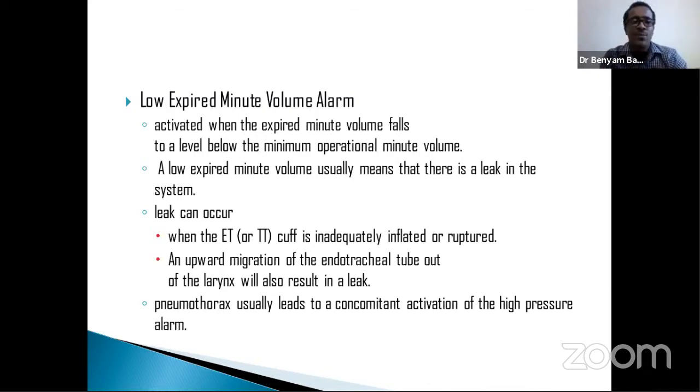Whenever we have a low expired minute volume alarm, usually this alarm goes off when the expired volume falls below a certain level. Technically it means you're losing air somewhere. The air is going into the lungs, but not coming out to be detected by the machine. So there's air loss in between. This usually happens due to leakage. Leakage usually occurs at the ET tube or the ET tube cuff or tracheostomy tube cuff, if it's inadequately inflated or ruptured.